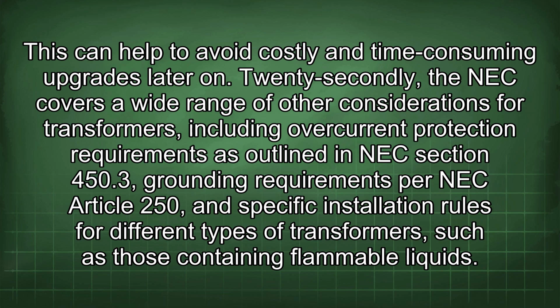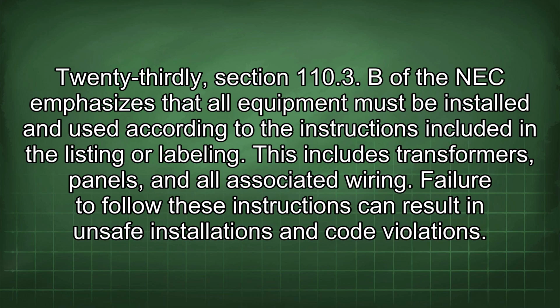22ndly, the NEC covers a wide range of other considerations for transformers, including overcurrent protection requirements as outlined in NEC Section 450.3, grounding requirements per NEC Article 250, and specific installation rules for different types of transformers, such as those containing flammable liquids.